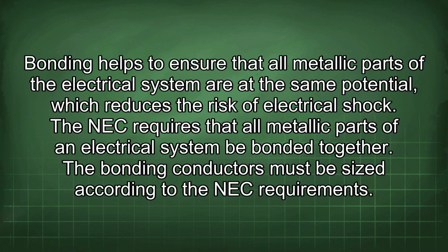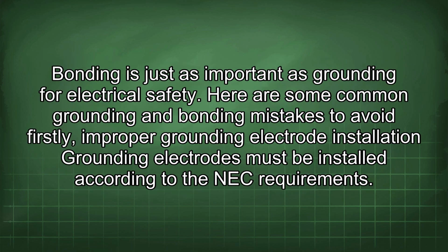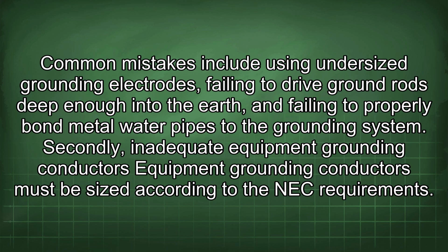The bonding conductors must be sized according to the NEC requirements. Bonding is just as important as grounding for electrical safety. Here are some common grounding and bonding mistakes to avoid. Firstly, improper grounding electrode installation. Grounding electrodes must be installed according to the NEC requirements. Common mistakes include using undersized grounding electrodes, failing to drive ground rods deep enough into the earth, and failing to properly bond metal water pipes to the grounding system.